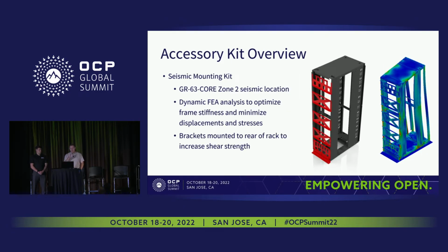There was a question earlier about seismic within the base specification, as it's not currently specified. We are developing a seismic kit for the Meta version of the rack, to be used in specific locations that may require it. This is not something we would put on every rack, or really the majority of our racks. There are a couple of different ways to implement this, but in this particular concept we've developed a bracket kit which will ultimately support GR63 core Zone 2 seismic locations.